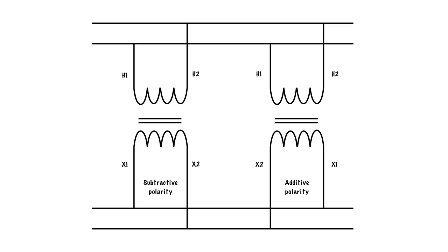In this video, we're going to be discussing paralleling single phase transformers. Remember, when it comes to paralleling transformers, there are three rules that have to be obeyed. Number one, you have to have the same voltage ratings of the transformer, and that has been covered in another video. Secondly, you have to observe the instantaneous polarity. That is not to say that they both have to be subtractive or both have to be additive, but that's what we'll discuss in this video. And thirdly, they have to have the same percent impedance.